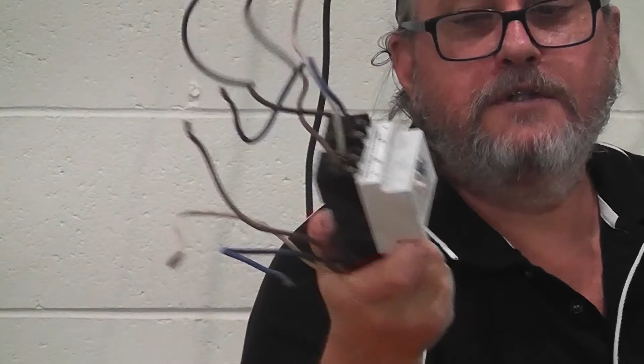So these things rely on the switchboard being wired correctly, and the main thing is that you've got the polarity right, so your active and your neutral are the right way around, and there's a MEN link between the neutral and the earth bar. There should be only one of those per earth stake. That then allows the RCD to operate. I've got another slide which shows you how they operate. I'm pretty sure you all know, but I'll take you through it.